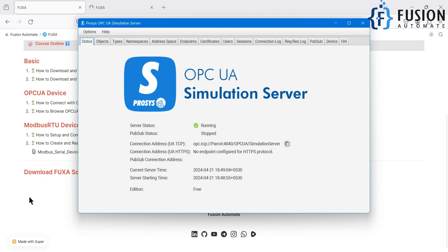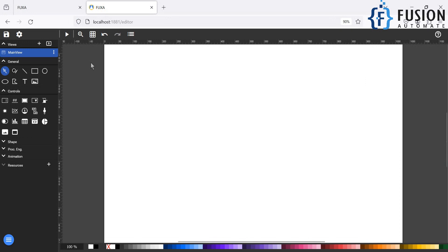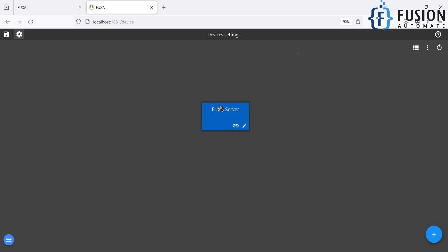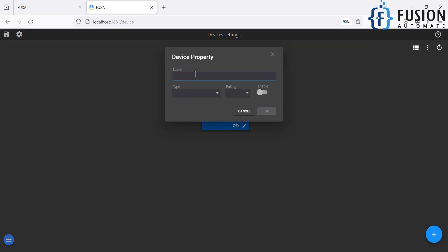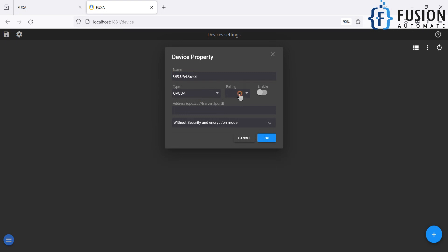Now we will navigate to the FUXA SCADA editor. In the Edit Project section, we will click on Connection and here we have to add the device connection for OPC-UA. I click on this plus icon — here is my OPC-UA device connection. The device type is OPC-UA, the polling interval is one second, and we will enable this device. Now we have to provide the endpoint URL of our OPC-UA server.